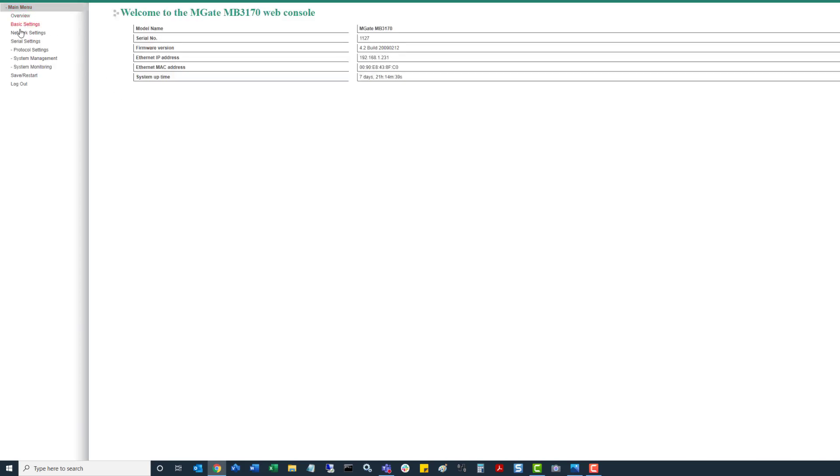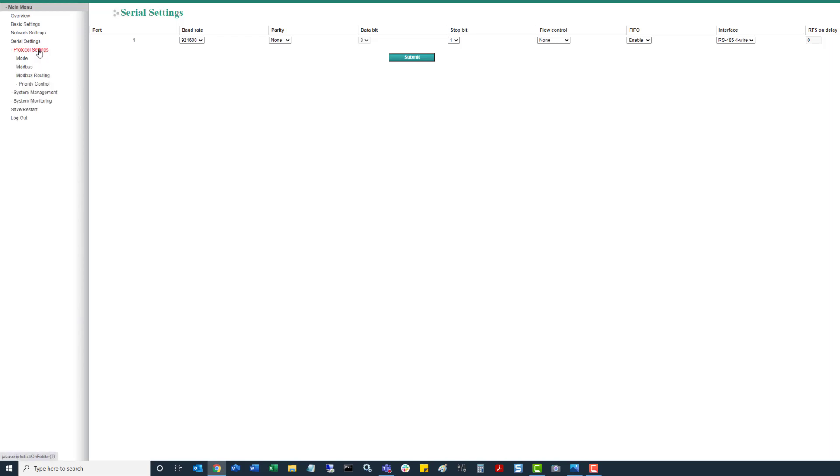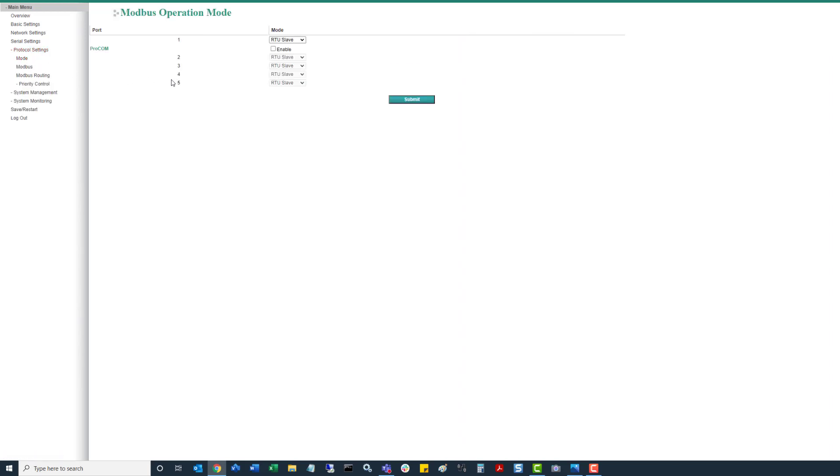So this is where when you come down to serial settings, I already went through and updated it, but you want to set it to that max baud rate, and then make sure all the settings match the Modbus RTU master unit. And then under protocol settings, make sure that that mode is set up to RTU slave.